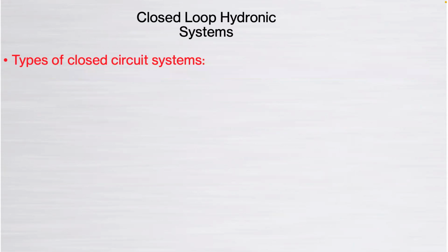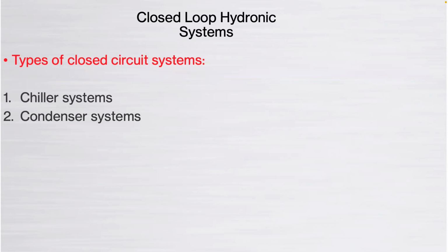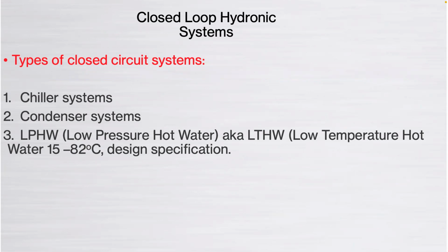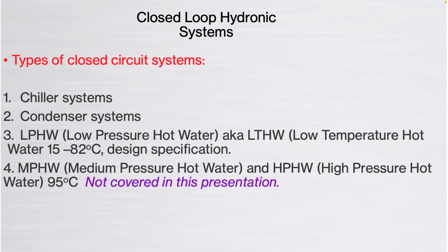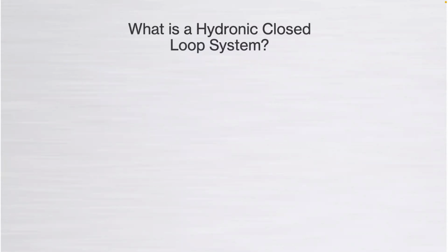The water quality we're talking about really pertains to closed loop hydronic systems. The types of systems we're talking about are chiller systems and condenser systems. These are closed loop condensers, so not your cooling tower open evaporative. And LPHW, so your usual temperature is around about, apologies, I don't know why that's in metric, I should have changed that, typically around 200 degrees Fahrenheit. What we don't cover is anything above 200 degrees. It's typically your medium pressure hot water or medium temperature hot water and steam, etc. That's not really covered in what we're discussing.